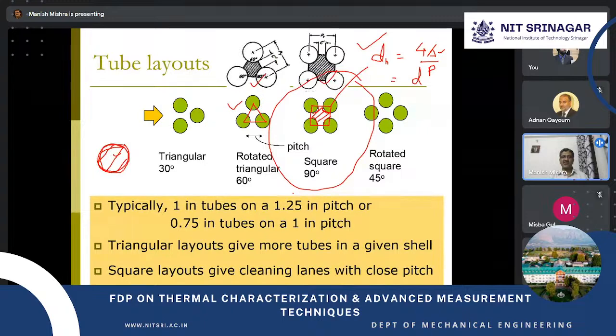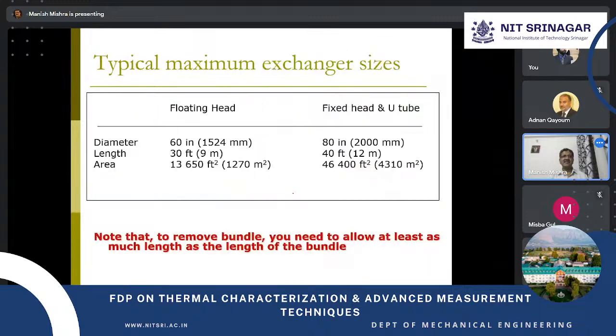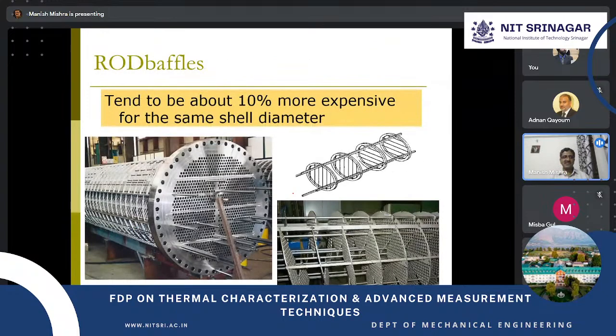Okay, so this is what has been shown here. Typical maximum exchanger size, this is there. Now this is one of the tube bundles, but apart from the tube bundle, what additionally I wanted to show is when I'm putting the baffles, what happens: the baffles, apart from increasing the residence time, also increase the pressure drop.